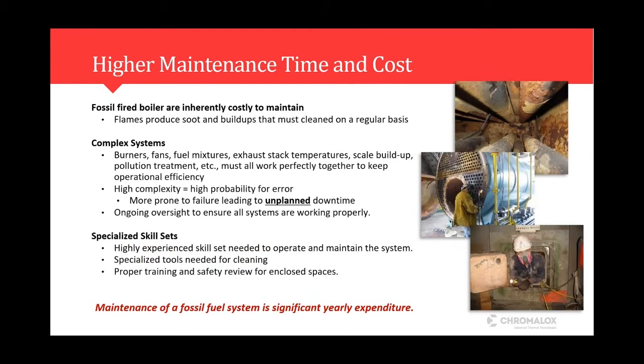We look at maintenance. This is a big factor for total cost of ownership as well. We've already kind of alluded to it in some of the slides here, but the fuel-fired systems are much more complex with the burners and the fans, oxygen metering, the flue stack. Often you need chemical treatment because the internal coils are typically comprised of standard wall carbon steel, which obviously over time, if that wears away, that's problematic. So you need some sort of treatment on that. So there's just a lot more that goes into these fuel-fired systems, which means that they have to be maintained on a more frequent basis. And also more complexity means more probability for error. So if there's a small failure, that might compound into other parts of the system, and that can lead you to an unplanned shutdown.